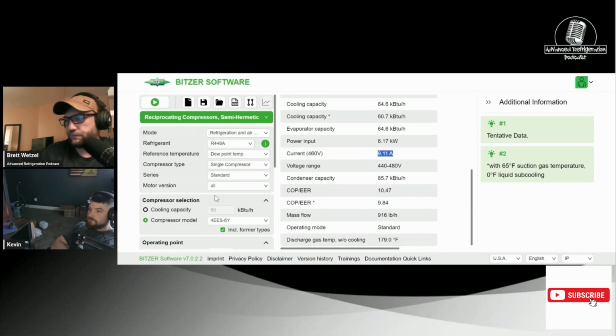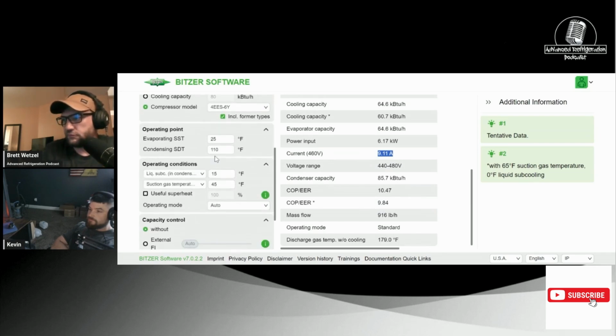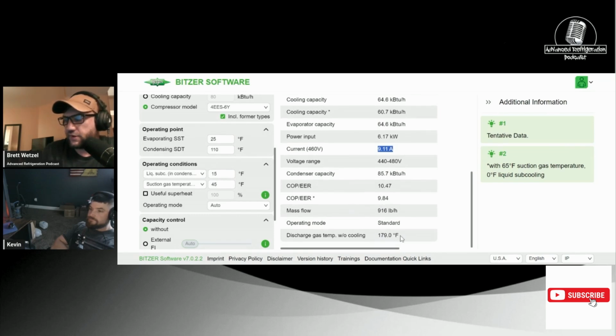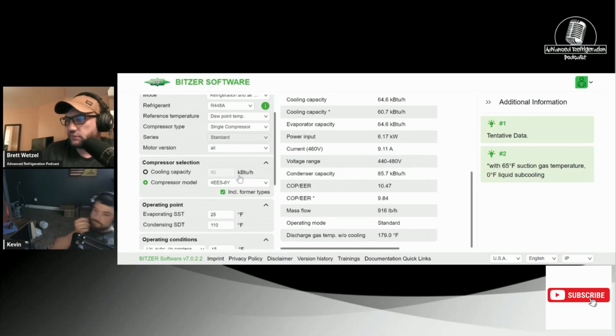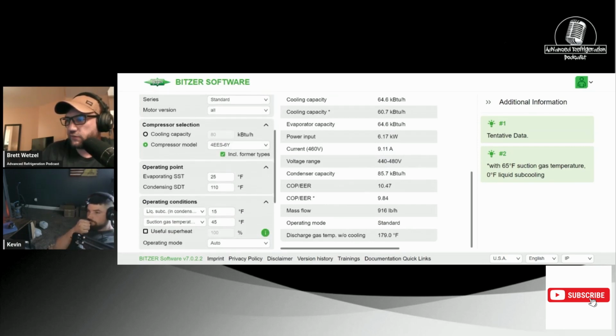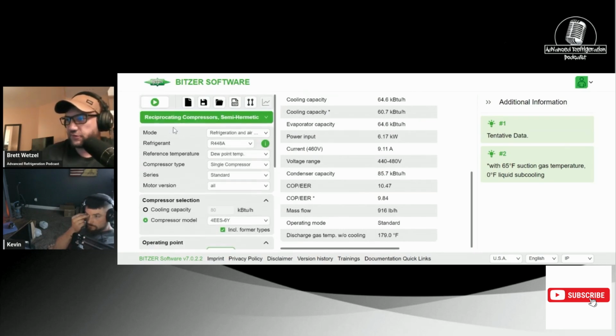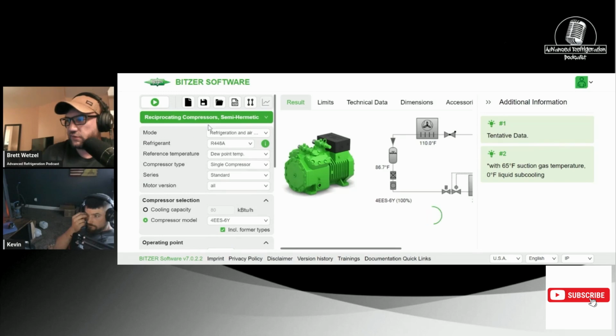.11 amp. 25 degree SST, liquid subcooling and condenser, nothing changed. 9.9. And head temperature went down a little bit more. Did the amperage go up or down? The amperage went up. Okay, 911. And then let me go back to 20 degrees saturated, because that was weird. Unless because I was going to change something else. Play.